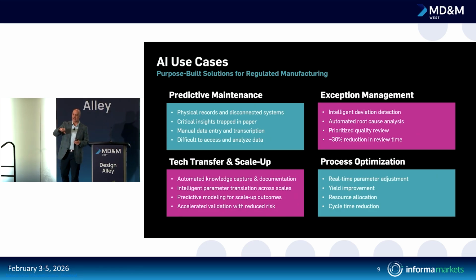If you think about the maintenance space, calibration, preventative maintenance, these things are typically done on a cadence. Why? Because it's the easiest thing for us to track. Now, if I could tell you that I can calibrate this instrument once every 18 months instead of every 6 months because of data coming off usage sensors, because of algorithms run against the drift that determine 6 months is just way too often, you don't need to do that. Now you reduce the cost of doing the maintenance, but you also increase the uptime of the machine because you're doing those activities far less frequently. So really good uptake on the predictive maintenance side.